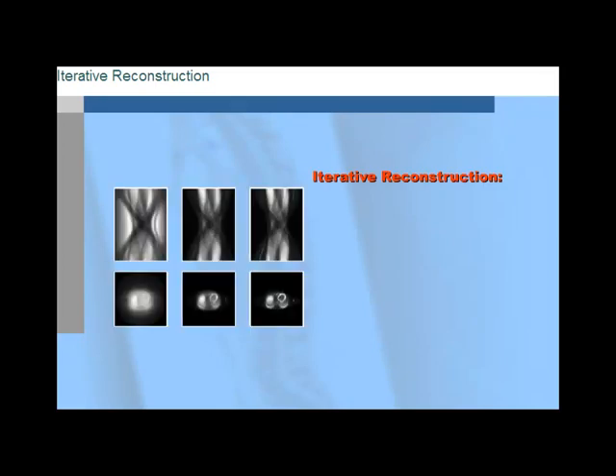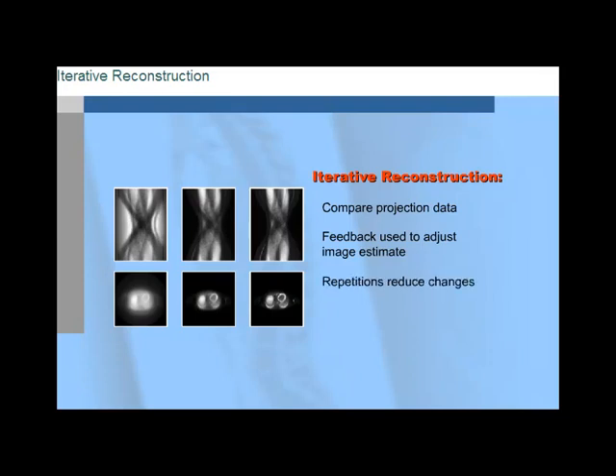Now we're ready for what we call IR, or iterative reconstruction. It's helpful to remember that the word iterative means repeat. The basic concept of IR is to compare the numerical projection data and the measured projection data in a feedback loop. The feedback from this comparison is used to adjust the image estimate and to minimize the difference between these two data sets. As the process is repeated, the derived changes to the image estimate become small and the estimate converges on the solution image. The number of iterations required to reach convergence is dependent upon which IR algorithm is utilized. Optimal resolution and contrast are used as a measure of convergence, and rapid convergence is a necessary prerequisite for practical clinical implementation.